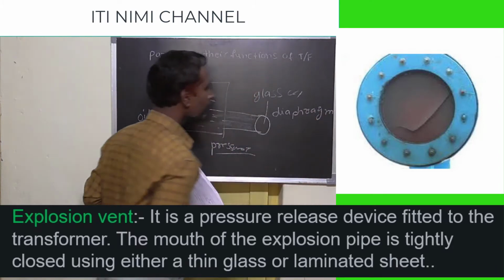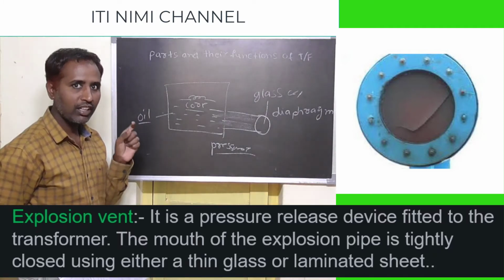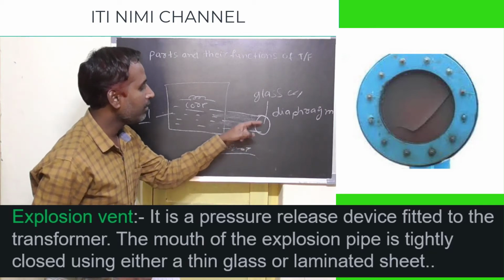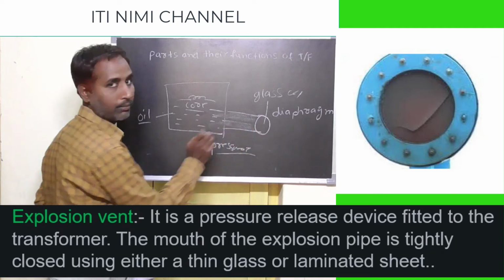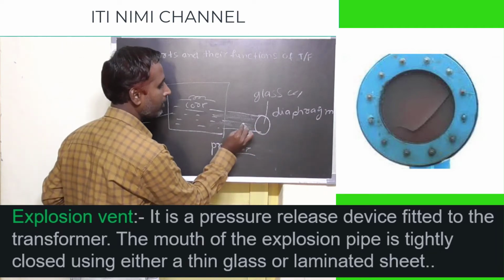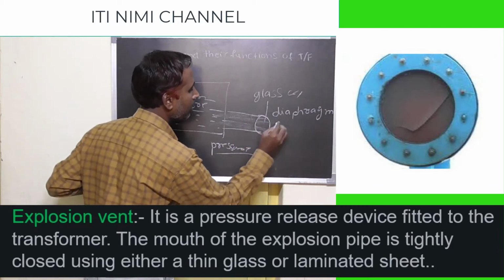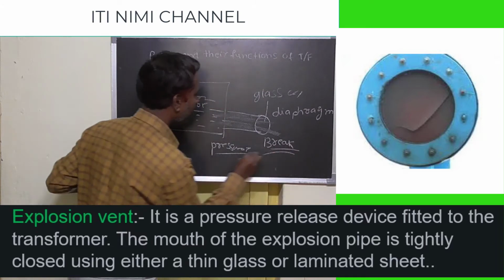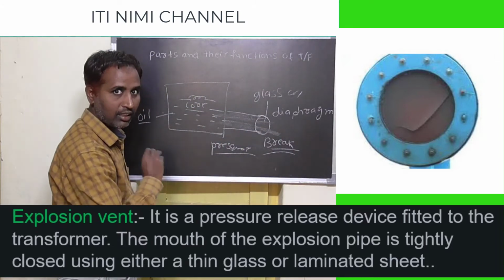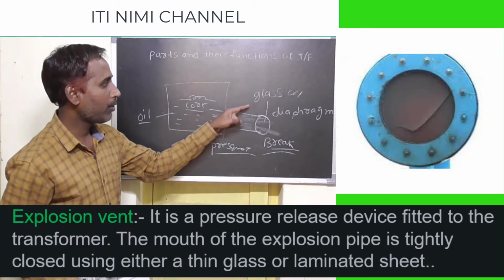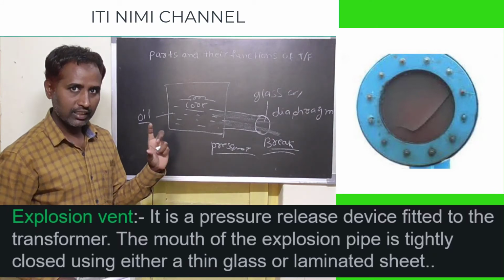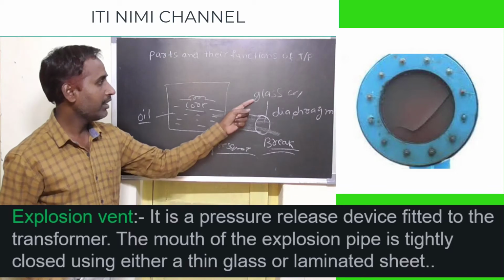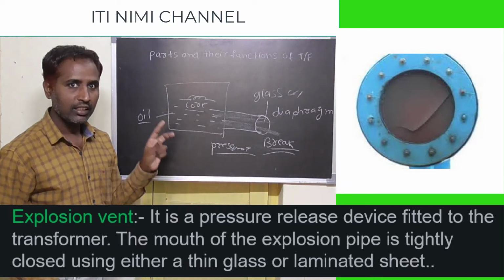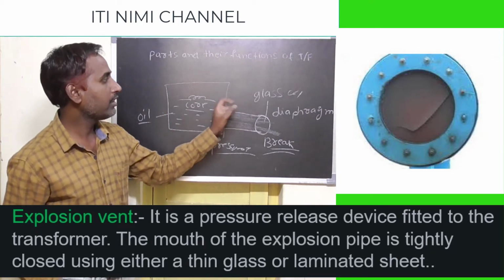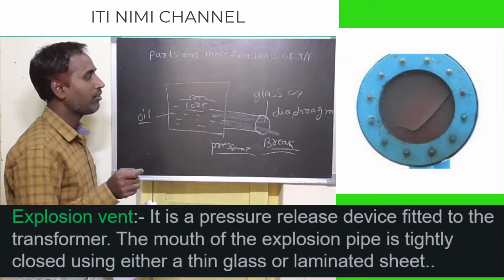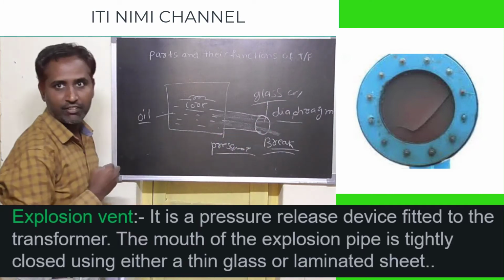In the examination, a question will come on the explosion vent material. What happens is, if pressurized oil comes into the explosion vent, this glass will break, and the transformer oil comes outside, releasing the pressure. This is a very important point: the mouth of the explosion vent is made up of glass or diaphragm material. In the exam, the question will come on this topic - the material is glass or diaphragm.